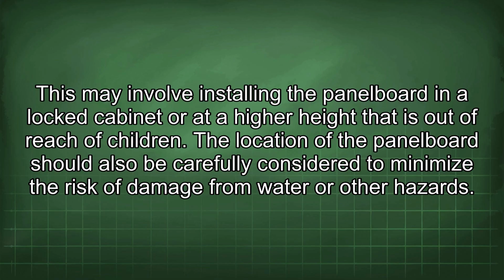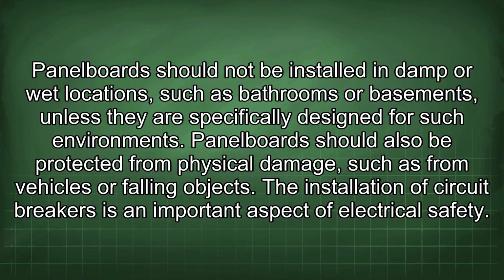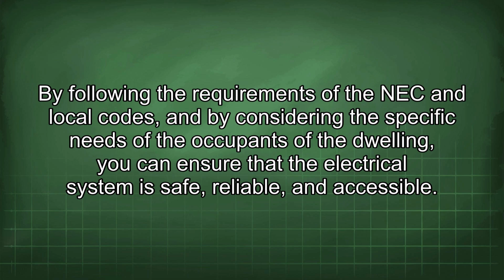The location of the panelboard should also be carefully considered to minimize the risk of damage from water or other hazards. Panelboards should not be installed in damp or wet locations, such as bathrooms or basements, unless they are specifically designed for such environments. Panelboards should also be protected from physical damage, such as from vehicles or falling objects. The installation of circuit breakers is an important aspect of electrical safety. By following the requirements of the NEC and local codes, and by considering the specific needs of the occupants of the dwelling, you can ensure that the electrical system is safe, reliable, and accessible.